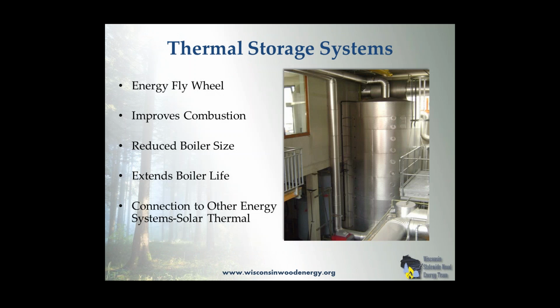Here's an example of thermal storage. This is a 2,000-gallon tank, and you can see that you have the line coming out of the top and the one going into the bottom. And basically, I think we're looking at the side that is on the boiler. The boiler draws off the bottom of the tank and delivers to the top of the tank. There are some rules of thumb, and lots of ways you can decide how to size thermal storage. But roughly, you're looking for about 15 minutes of the capacity of the system in a chip system in the thermal storage tank, or a rough rule of thumb is about 75 to 100 gallons for every 100,000 BTUs of capacity.